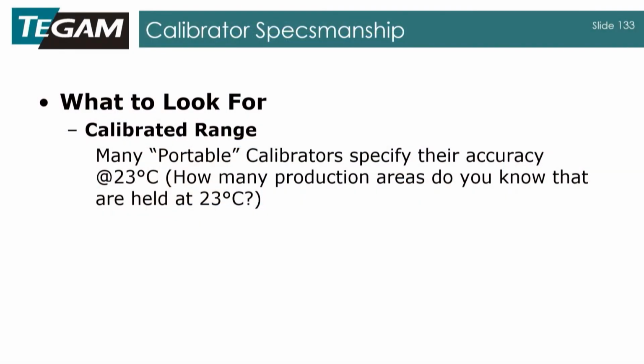One thing to look for when you're looking at calibrators, since there are a number of them out there from different companies, is that we talked about all those things that cause errors in a temperature measurement, and Tempco is one of them. Many specify their accuracy at 23C, but you have to account for any deviation from that 23C, since it's part of the Tempco. So you want something that operates over a wider range and still maintains its specifications, or at least you have to account for that in your uncertainty budget, especially in field production work. Look for something that operates over a reasonably wide range.